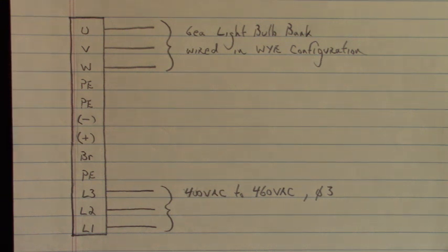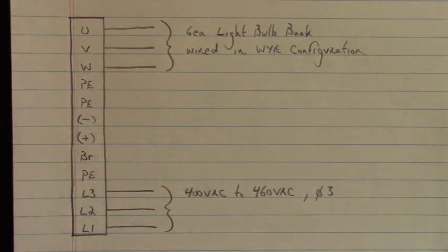Very nice. Now if you don't have a light bulb bank or the spindle motor, you can look at U, V, and W with no connection with your oscilloscope. I like to use the Fluke oscilloscope because I'm isolated from earth ground. There's no chance of this high voltage shooting back up to earth ground through my oscilloscope if I use that Fluke. It's disconnected from earth ground.